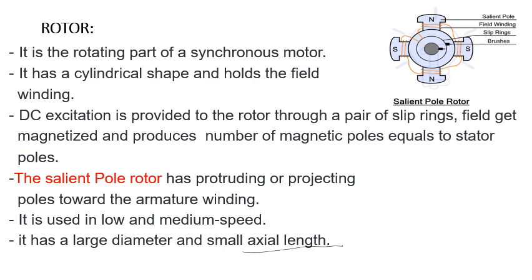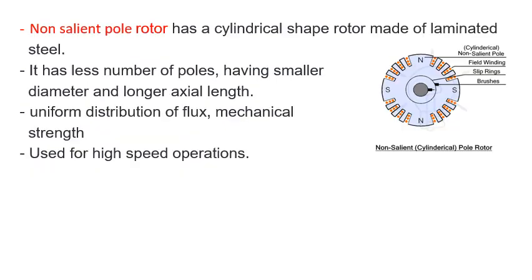We have already discussed the difference between salient pole and non-salient pole type machines in a previous video — you can refer to that for more details. In this slide you can see a non-salient pole type rotor. Here the poles are not projecting, hence they carry the name non-salient pole type machine, or otherwise smooth cylindrical pole type machines. These rotors are normally used for high speed operations and they have a smaller diameter and longer axial length.